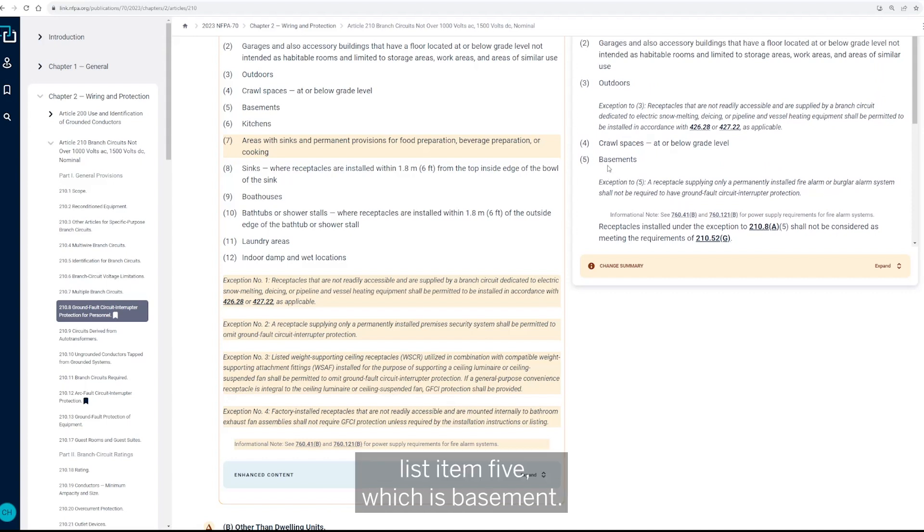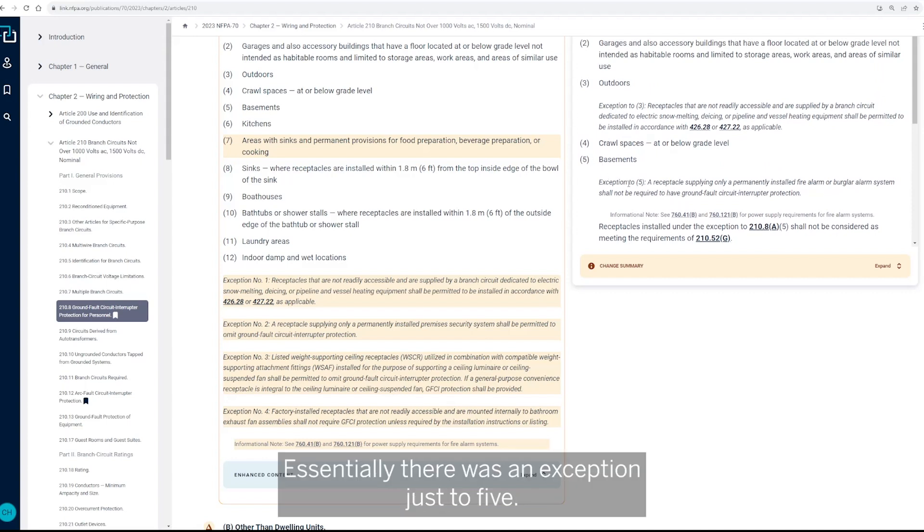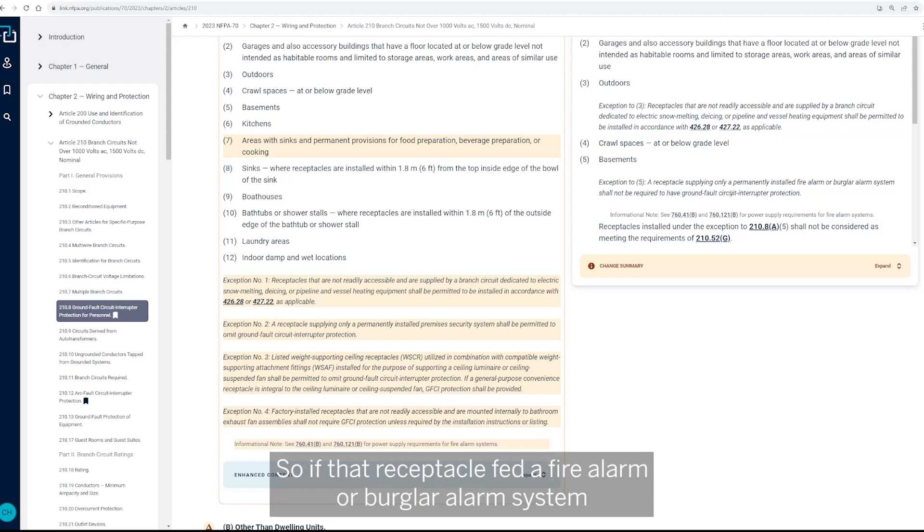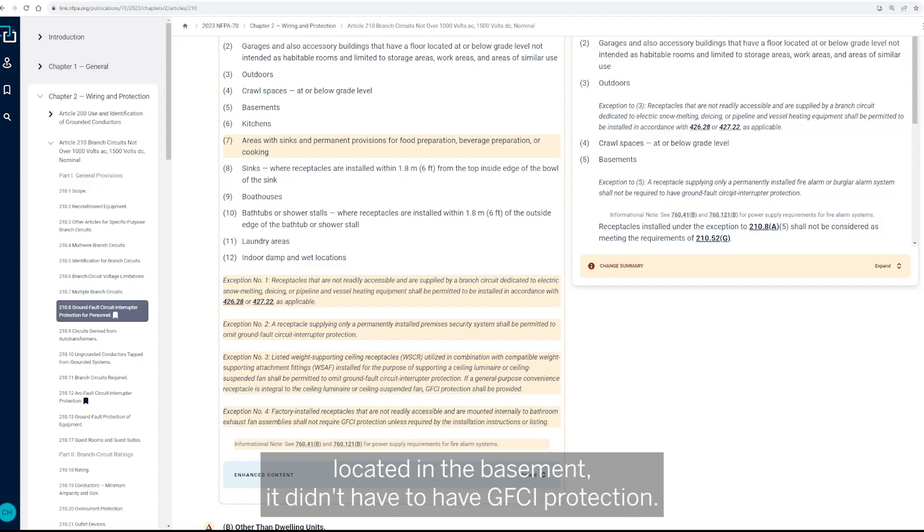So that was in the 2020. If we go back up here, but it was located under sub item five or list item five, which is basement. So essentially there was an exception just to five. So if that receptacle fed a fire alarm or burglar alarm system located in the basement, it didn't have to have GFCI protection.